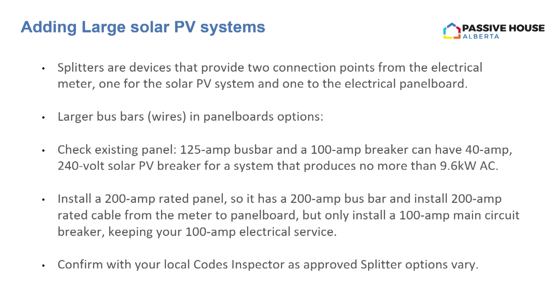And here's just some calculations with your 125 amp bus bar and 100 amp service, or a 200 amp bus bar and 100 amp service, which are two options if you have to replace the panel: put in a bigger panel, but still keep that 100 amp breaker. And again, confirm this with your local code inspectors to make sure it's acceptable before you go out and buy the equipment.